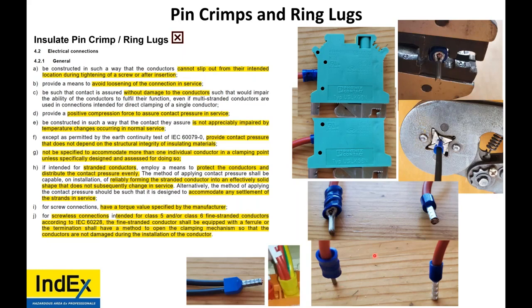Does not be impacted by temperature changes. Well, there's more surface area on a ferrule. Yeah, vibrations, temperature changes, it has more surface area to remain attached. Provide contact pressure that does not depend on the structural integrity of the insulating materials. Well, with the pin crimp, the insulation has a lot, that collar acts as a means of keeping that core from moving around too much. So once again, it doesn't meet the standard.